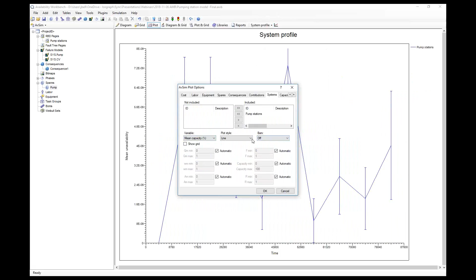Capacity over time — it looks like big jumps, but notice the Y scale: we're only looking between 98.4% and 98.95%. So it's jumping around, probably as things wear out, since there's a predictable wear-out pattern to the pumps and valves. These jumps aren't that big — within 0.2% for most of these waves.